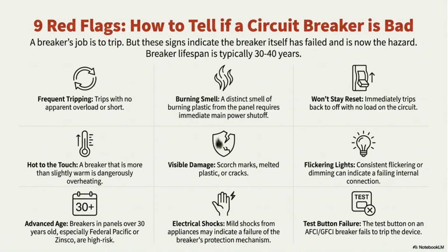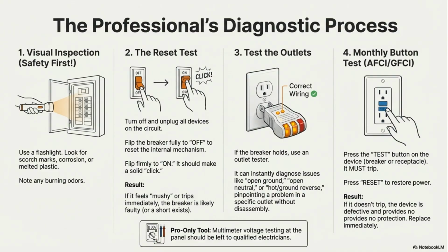A circuit breaker's job is to trip, but 9 red flags indicate a failed hazardous breaker. These include frequent tripping, a burning smell, visible damage, and failure of the test button. Breakers over 30 years old, or those that feel hot to the touch, are high risk. The professional diagnostic process involves 4 steps. First, perform a visual inspection for damage. Second, execute the reset test. If it feels mushy, the breaker is faulty. Third, test the outlets to pinpoint issues. Finally, perform the monthly button test on AFCI, GFCI devices.